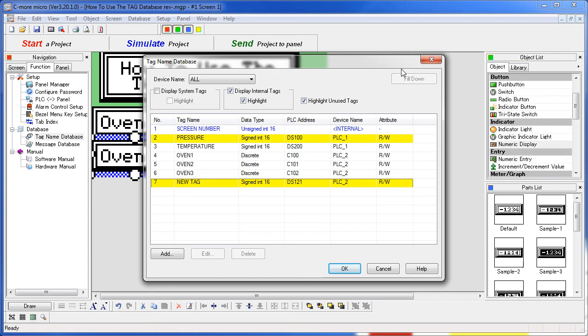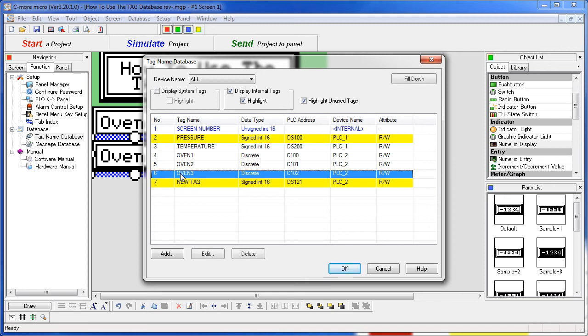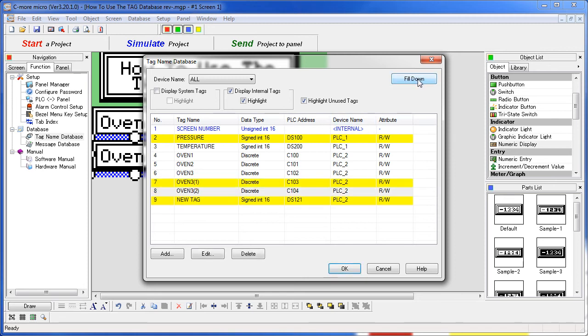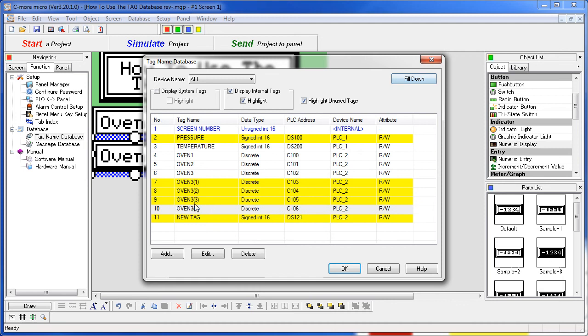The fill down button is handy if you have a sequence of tags. Suppose we wanted to add some more Oven tags for example, just hit fill down and it automatically adds tags with an index appended. Note that this only works for external tags, not internal C-more Micro tags because there is no memory address to increment with the internal tags.